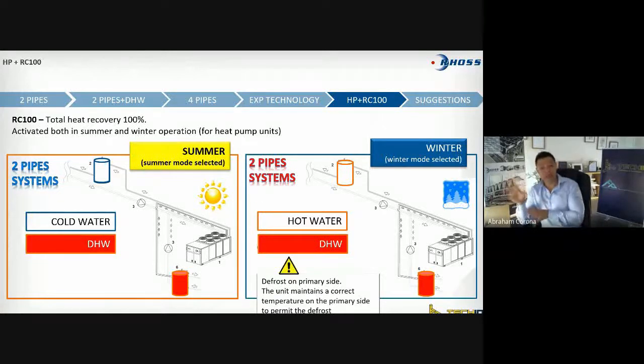And depending on the humidity in the environment, you can start to produce frost. You can start to frost the condenser fins externally, and that will continue growing and even block the coil. That is the reason any heat pump has what we call a defrost cycle. I will explain in the future how we do it, but basically we reverse the cycle and heat the condenser. We work like a chiller and we defrost the condenser.